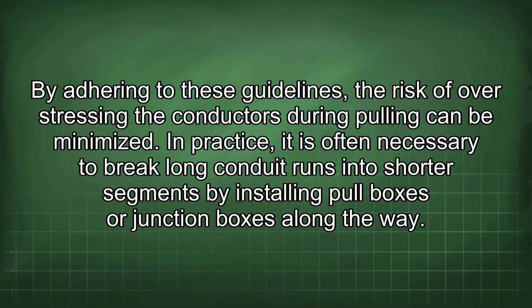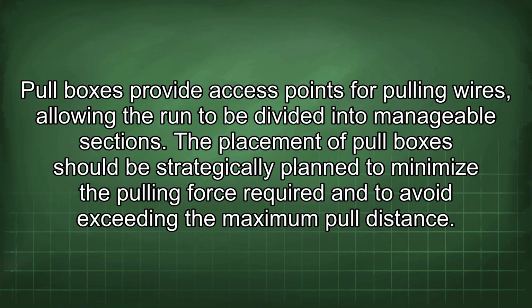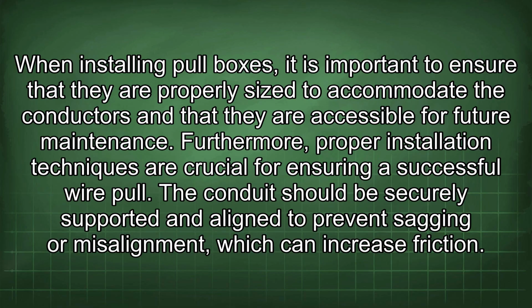In practice, it is often necessary to break long conduit runs into shorter segments by installing pull boxes or junction boxes along the way. Pull boxes provide access points for pulling wires, allowing the run to be divided into manageable sections. The placement of pull boxes should be strategically planned to minimize the pulling force required and to avoid exceeding the maximum pull distance. When installing pull boxes, it is important to ensure that they are properly sized to accommodate the conductors and that they are accessible for future maintenance.